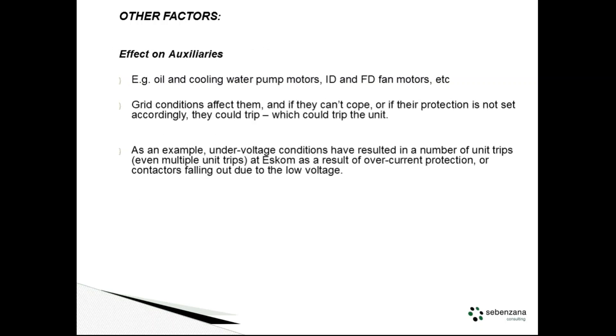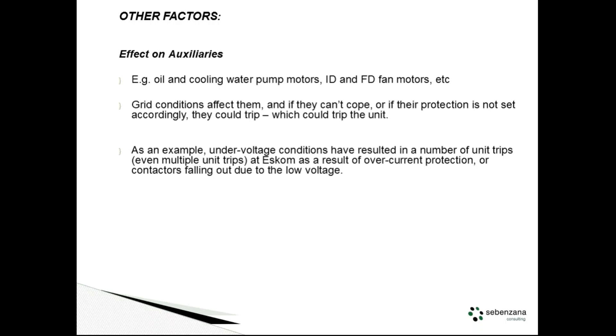One thing I've mentioned already but we mustn't forget: the auxiliaries are also connected to the grid. Any issues with the grid have to be handled by the auxiliaries. If they fail, the machine goes out. There have been a number of trips in Eskom where under-voltage conditions caused over-current protection to come in, contactors fell out, machines were lost, and they had multiple unit trips as a result.